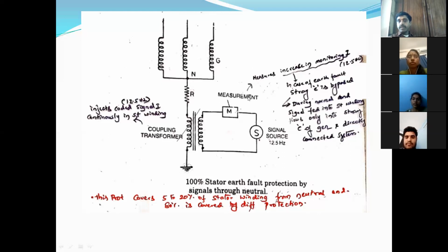This measurement measures the increase in monitoring current. In case of earth fault, the stray capacitance is bypassed. You know what the stray capacitance is? Stray capacitance means the line to ground capacitance, whatever is there. For low frequency signals, what happens? The capacitive reactance is 1 by 2 pi f C. When the frequency is very low, this capacitance is bypassed.